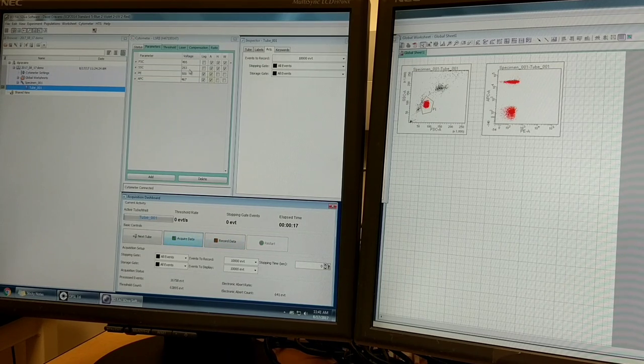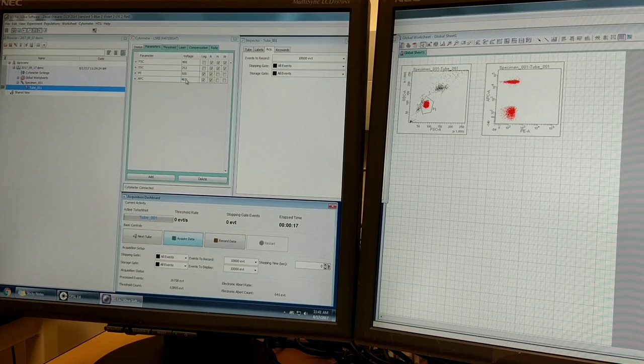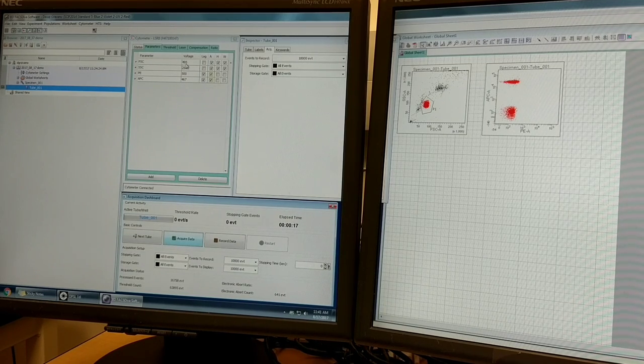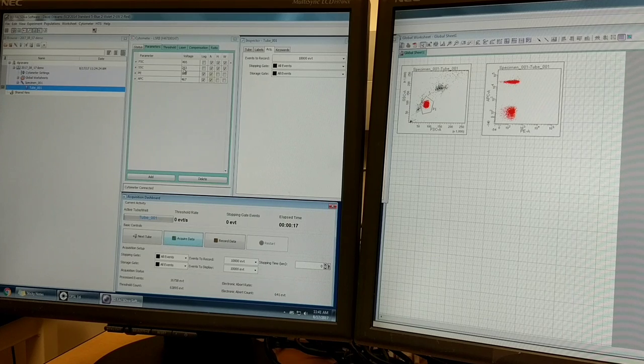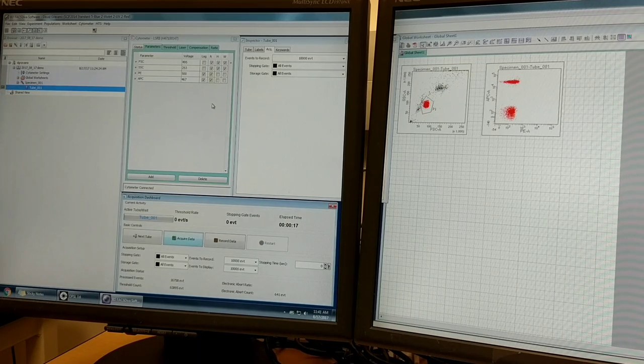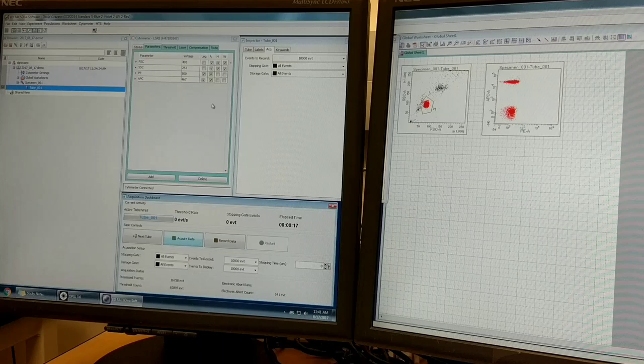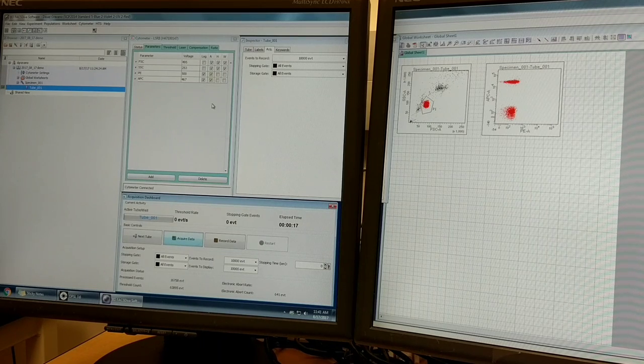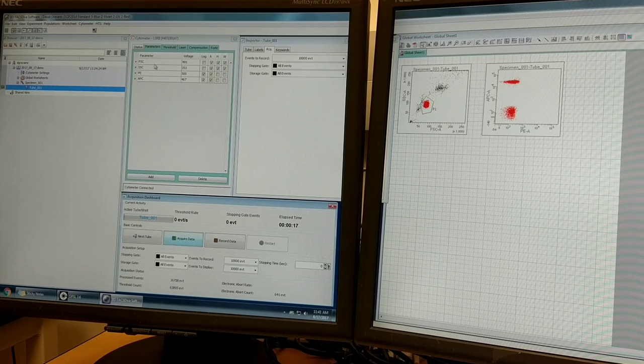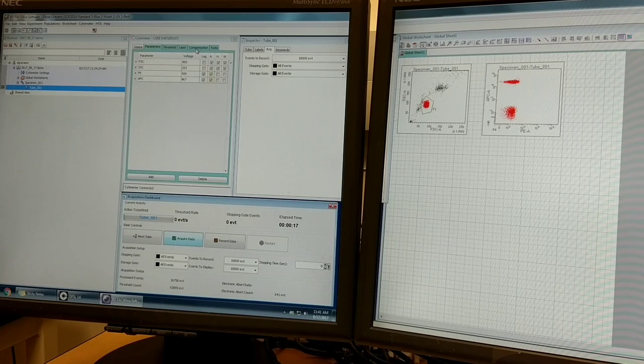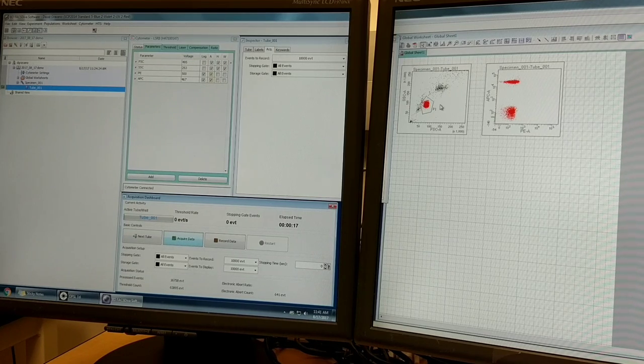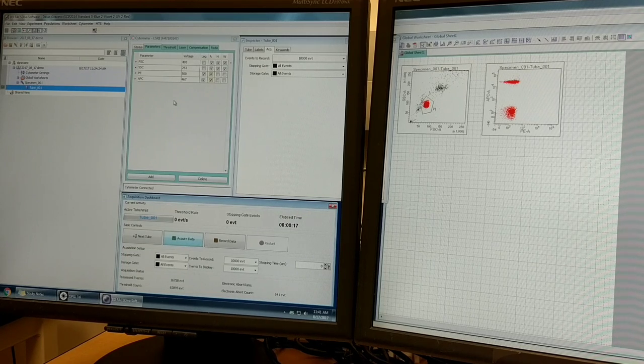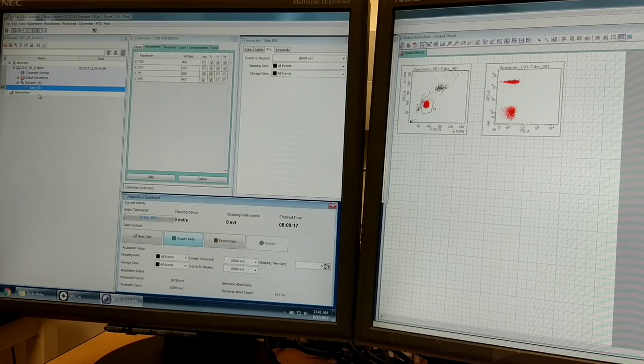I'm going to stop acquiring, and notice all these voltages are going to stay the same as what I've set: 467 for APC, 500 for PE. My forward and side scatters are now 495 and 253. So now I've set my voltages, I've got all the right parameters I want. In the case of PE and APC, there's no compensation needed, so I'm going to skip that step. I'm now going to show you how to acquire your fully stained sample.